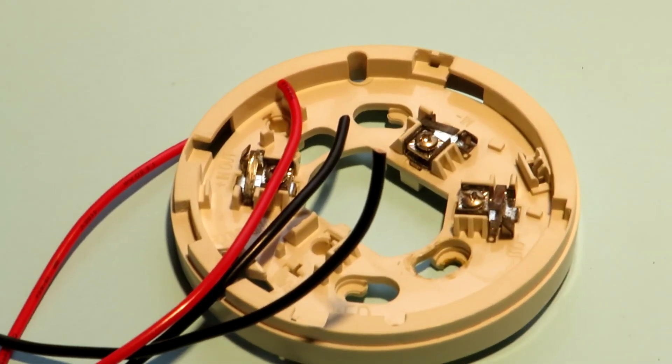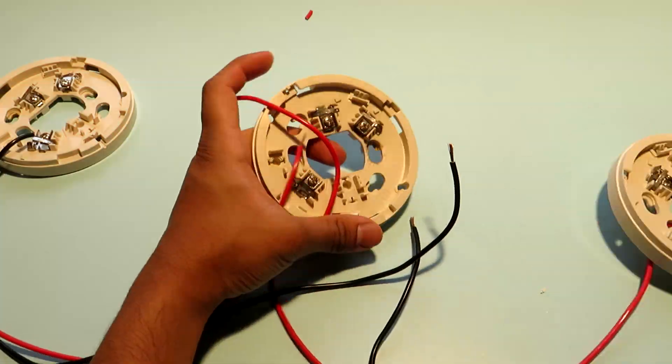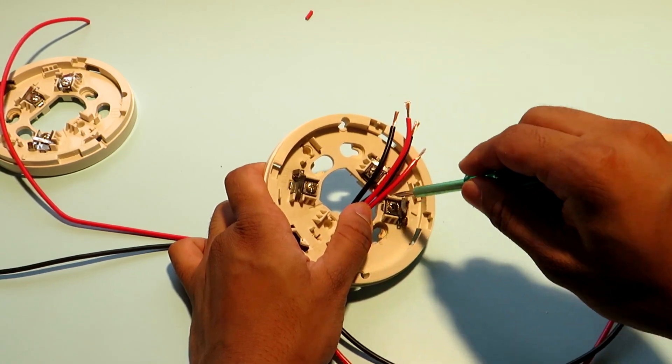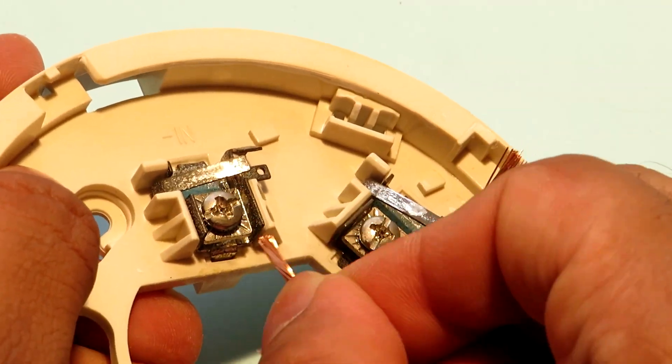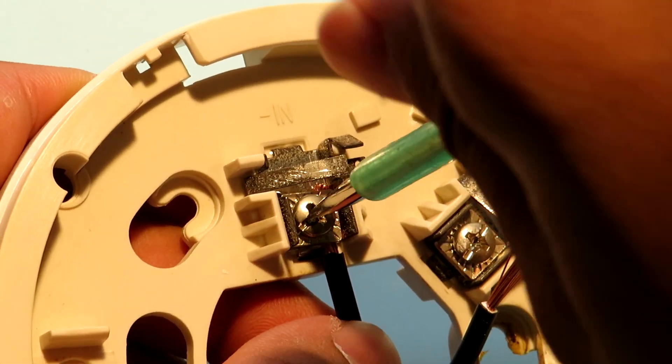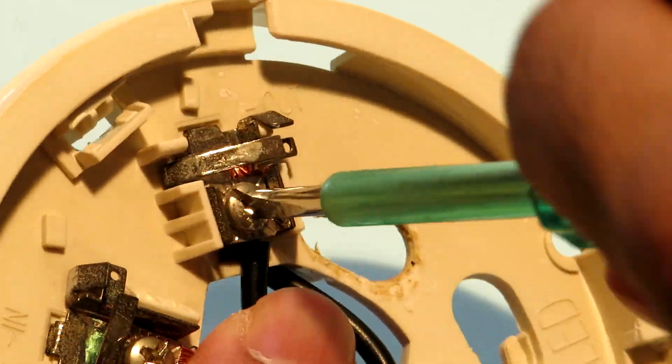Now let's connect the second detector. It's pretty much the same. Both the positive wires go to the same terminal which is labeled positive in out and the incoming negative wire from the first detector will go to the negative in terminal and the outgoing negative wire to the third detector will go to the negative out terminal. And it doesn't really matter even if you interchange these negative in and negative out terminals.